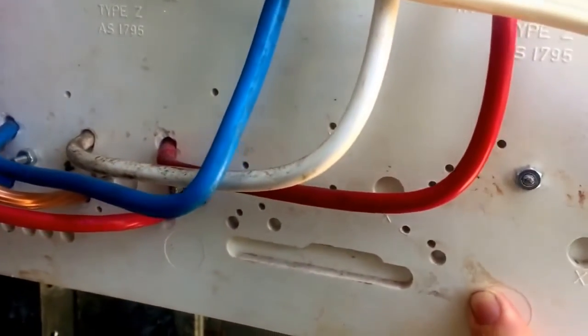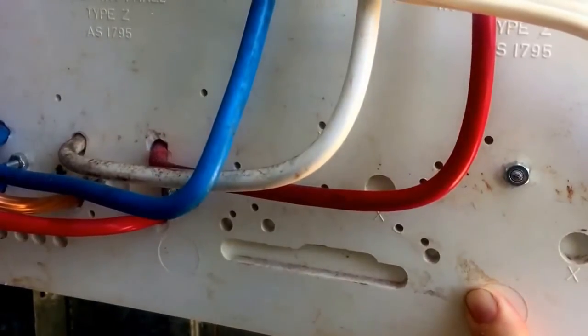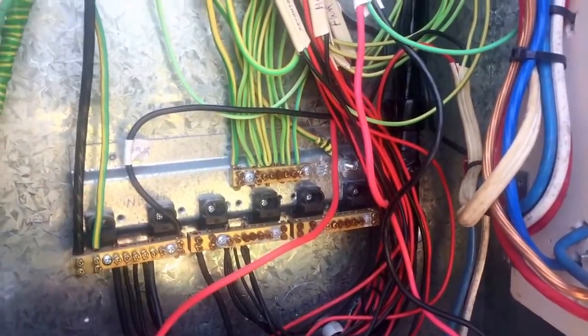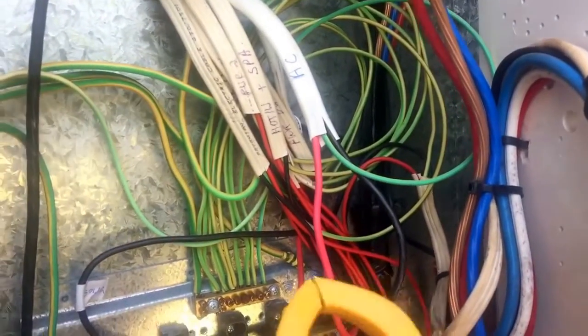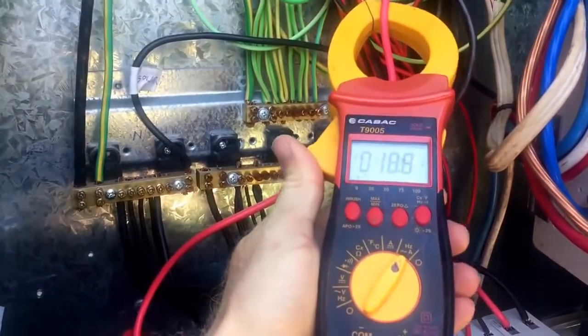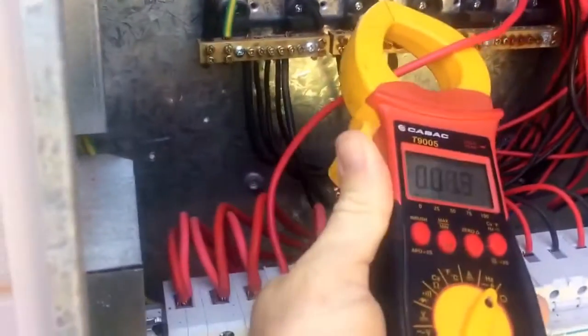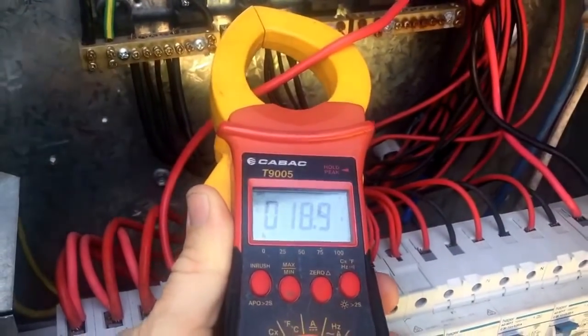We're just tonging the three-phase mains and these are the amps we're getting from the grid. Then we'll turn the solar off and see what happens to those amps from the grid. Our main load today is going to be the air conditioning because it's such a warm day. With the tong meter you can see 18.8 amps being used by the air conditioner and 18.9 amps being produced by the solar.